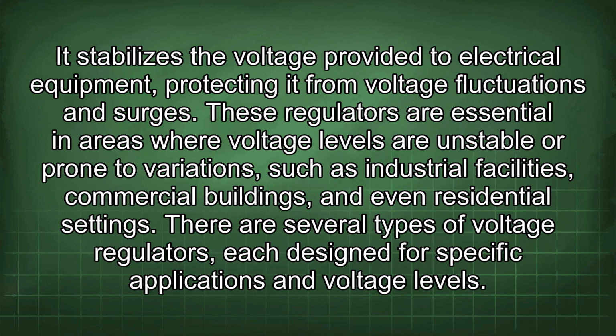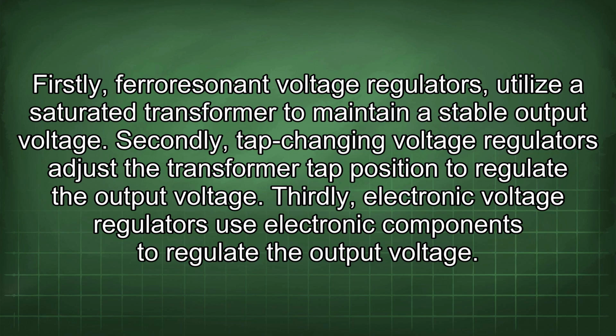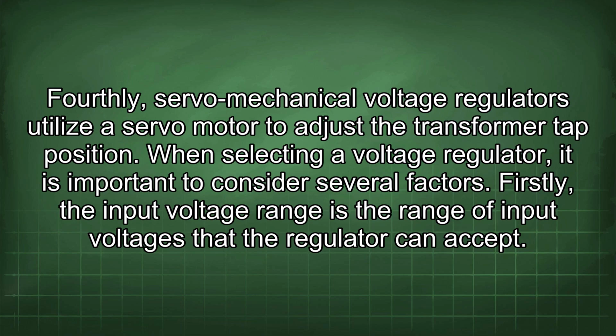There are several types of voltage regulators, each designed for specific applications and voltage levels. Firstly, ferroresonant voltage regulators utilize a saturated transformer to maintain a stable output voltage. Secondly, tap-changing voltage regulators adjust the transformer tap position to regulate the output voltage. Thirdly, electronic voltage regulators use electronic components to regulate the output voltage. Fourthly, servo-mechanical voltage regulators utilize a servo motor to adjust the transformer tap position.